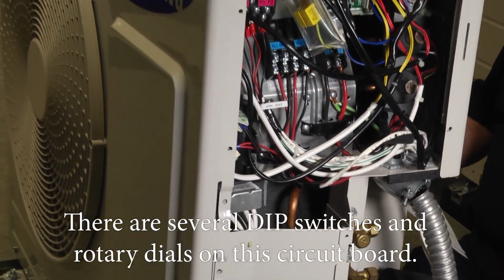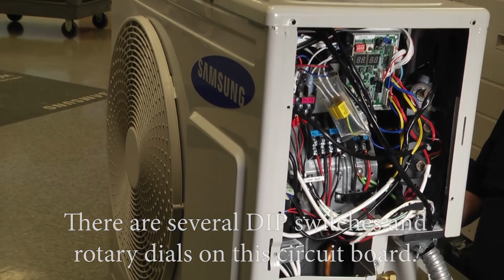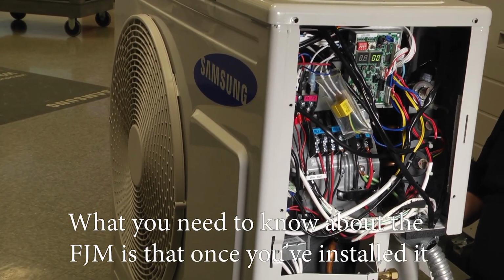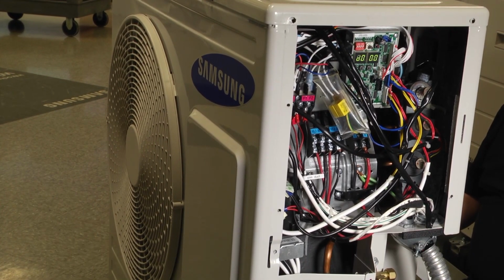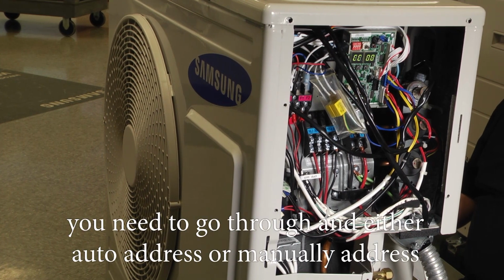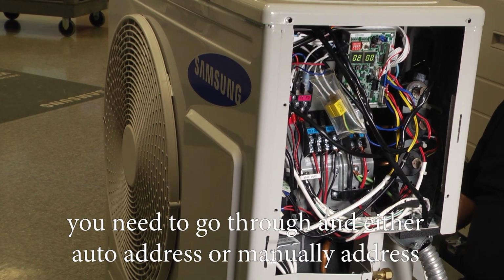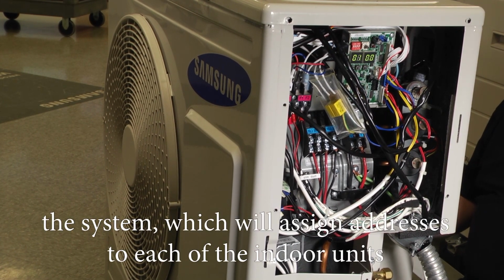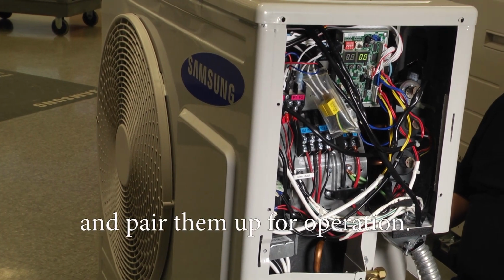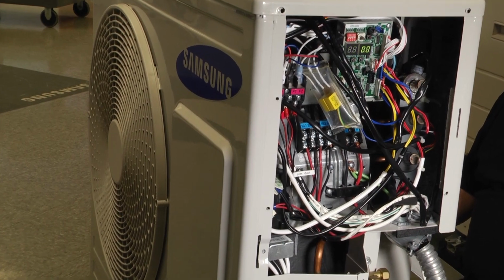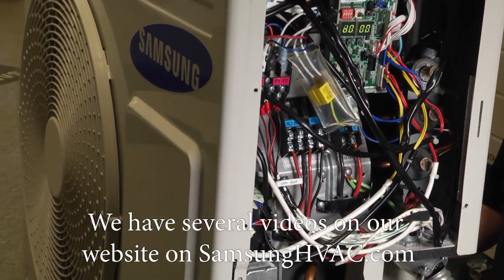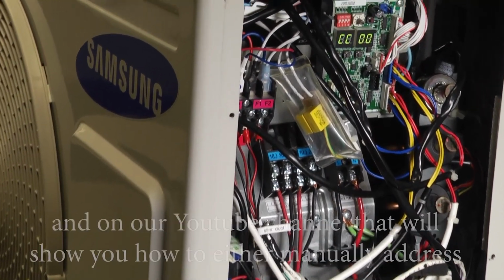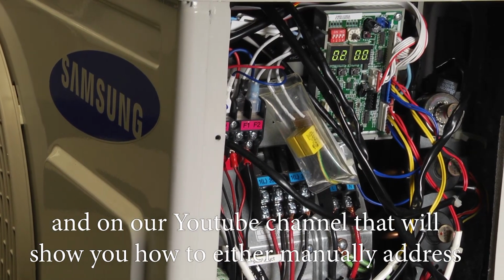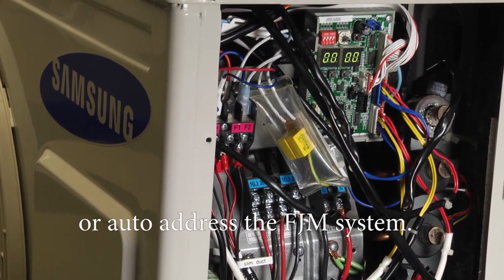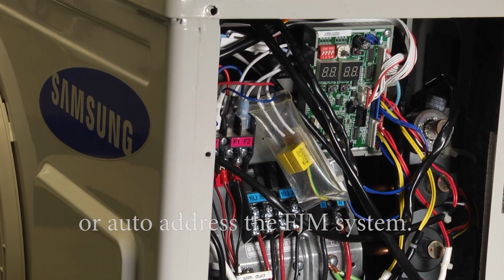There's several dip switches and rotary dials on this circuit board. What you need to know about the FJM is once you've installed it and you power it up, you need to go through and either auto address or manually address the system, which will assign addresses to each of the indoor units and pair them up for operation. We have several videos on our website on samsunghvac.com and on our YouTube channel that will show you how to either manually address or auto address the FJM system.